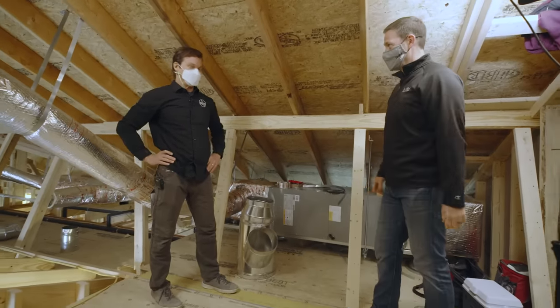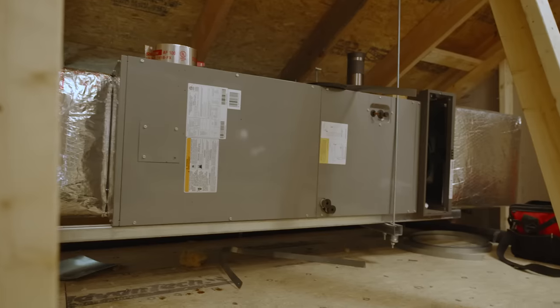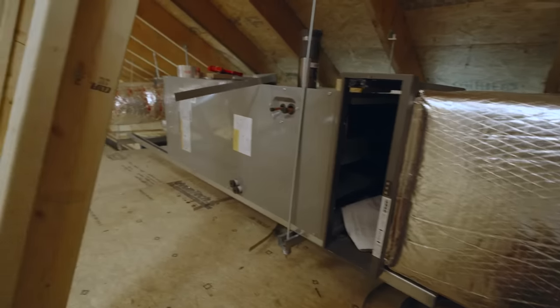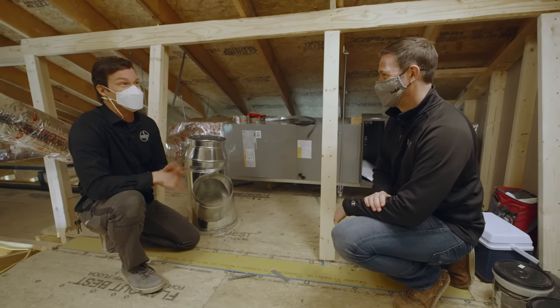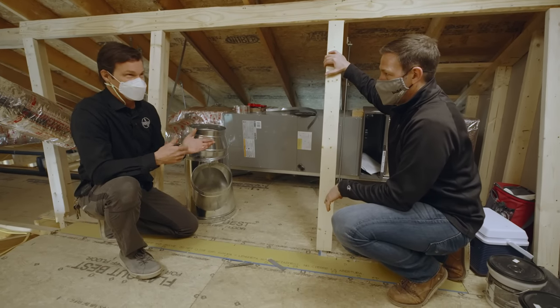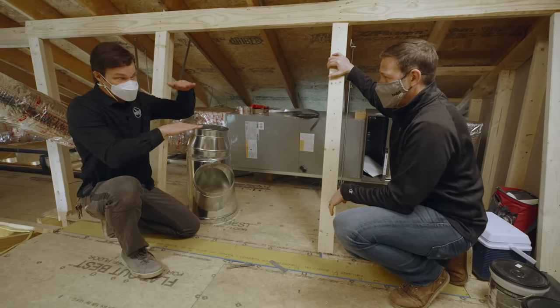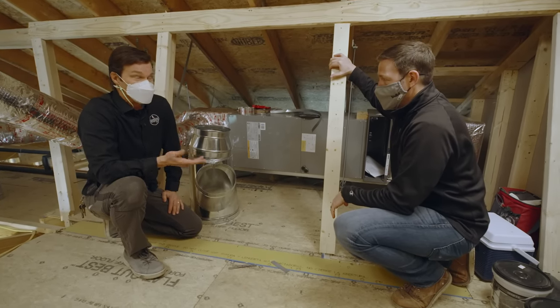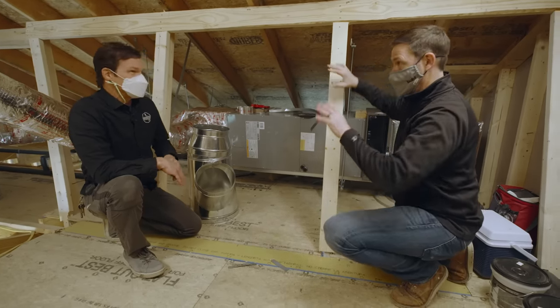Christoph, why is this box different than the standard heat pump box that grandma has in her house? Output supply temperature was the first thing that comes to mind. Do not confuse modern heat pumps with old heat pumps. Old heat pumps had supply temperatures that were above your thermostat set point but below your skin temperature — so with a bunch of air flowing around below skin temperature, it's a comfort complaint. To this day, heat pumps suffer from that unfair comparison from the 80s. But this unit is blowing hot air — upper 90s or even low 100s.